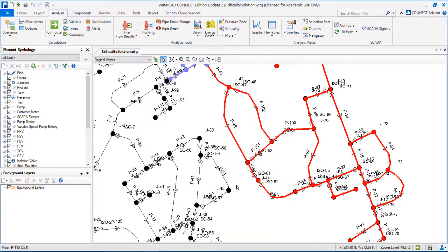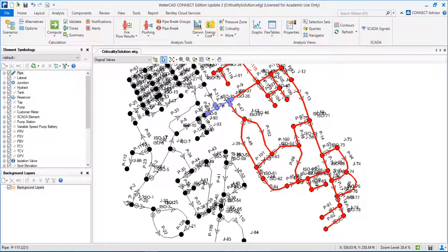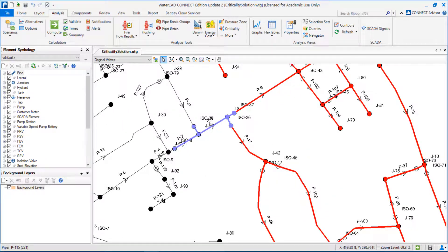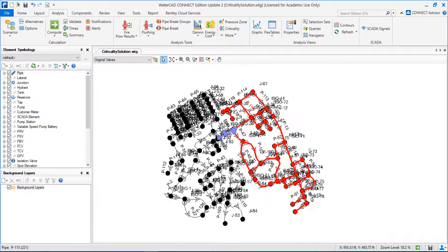Another more effective solution would be to create more redundancy or more looping in this system. I could try to join or connect this node to this node, for example. Probably, the cost of this would compensate the risk or the consequences when I have to close this pipe.